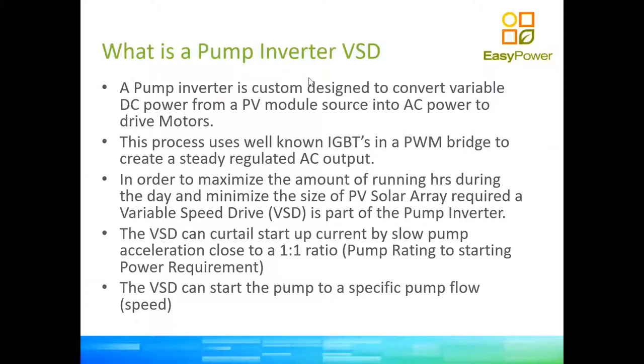A pump inverter or VSD is a variable speed drive that takes DC power, converts it to AC, and runs your pump. The smaller VSDs have PWM control units and IGBTs to regulate the AC output — it's a well-known pulse-width modulation technology. In order to maximize the hours the inverter pumps during the day, the inverter changes the frequency, because the power required by a centrifugal pump is proportional to the flow, the head, and the speed of the pump. A submersible pump is most often a centrifugal pump, though there are also progressive cavity pumps which behave slightly differently.